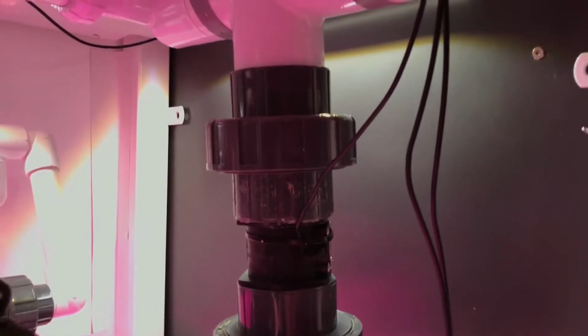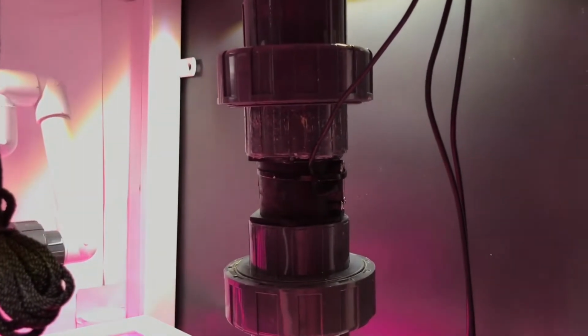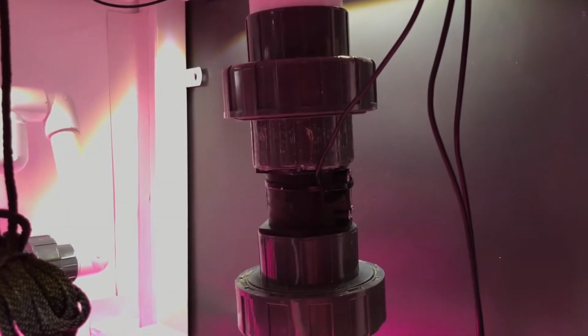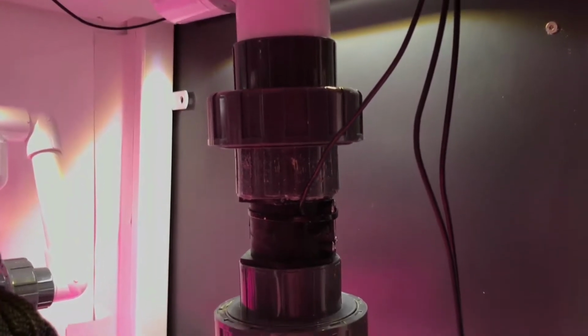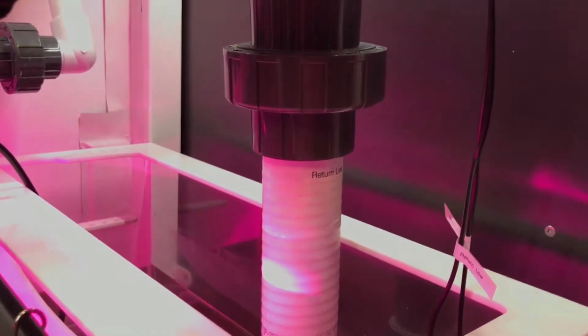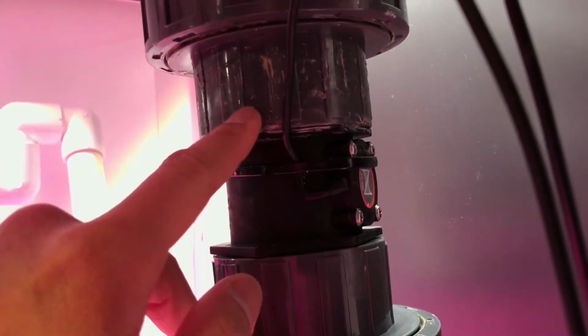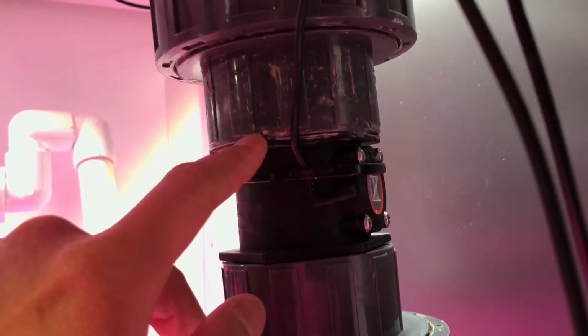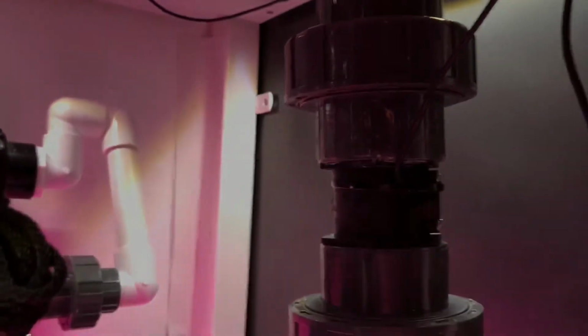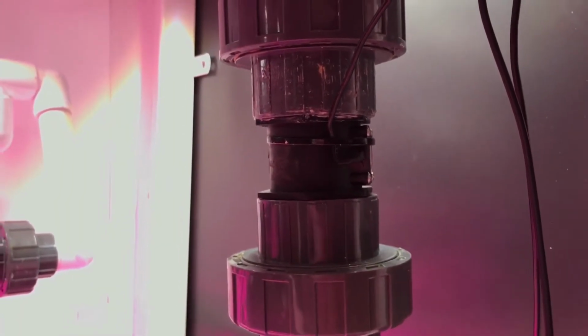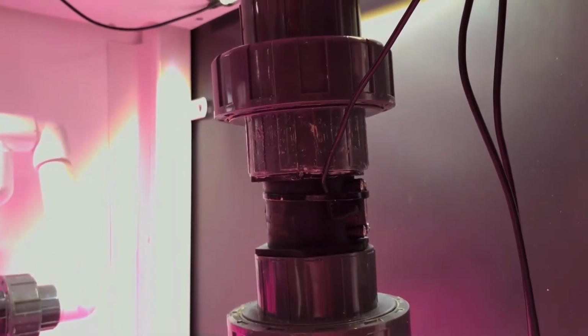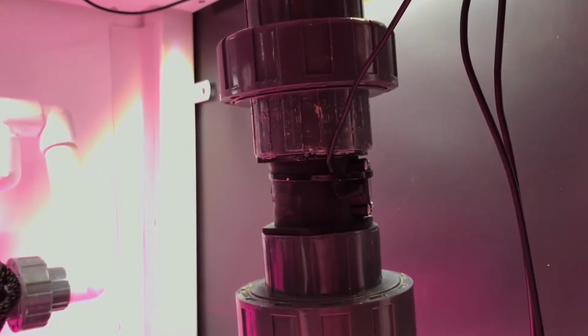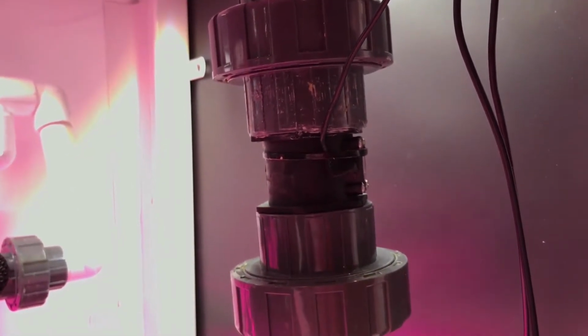Had the same problem over here, and then my other leaks were at the unions. You can see how badly I've marred this up because I kept taking it on and off. This is a 2-inch flow sensor from Neptune, and I could not get it to seal between the actual flow sensor and again this sort of universal adapter. I tried Rectorseal, then Plastostick, and finally just gave up and went back to silicone, and sure enough it sealed it. So here we are, all sealed up.